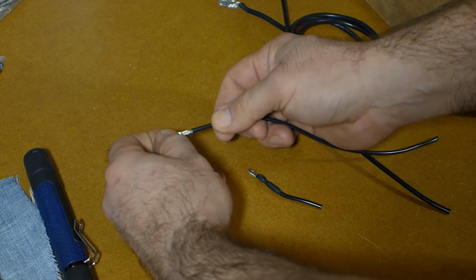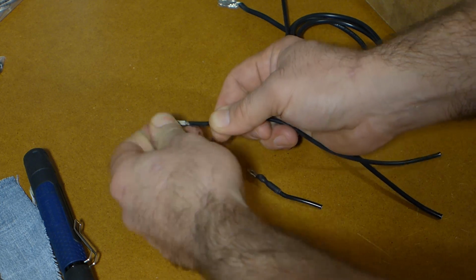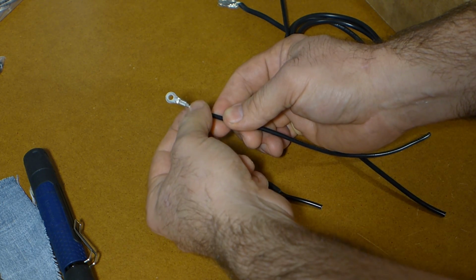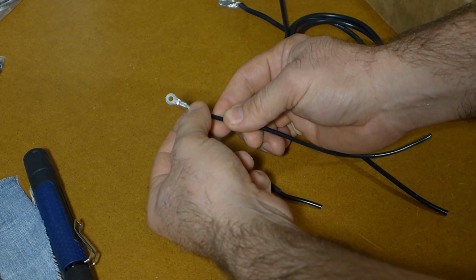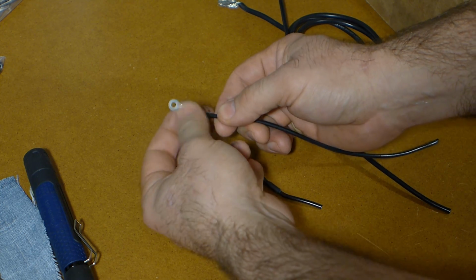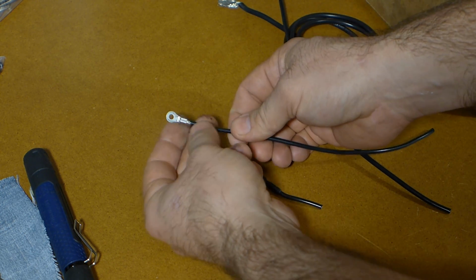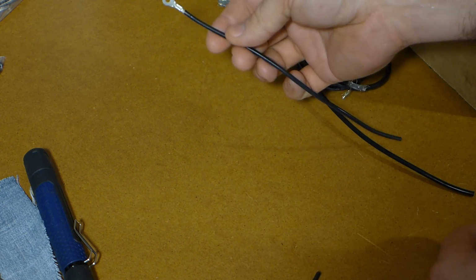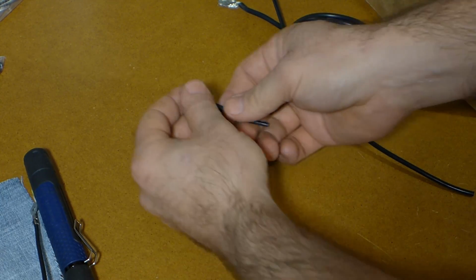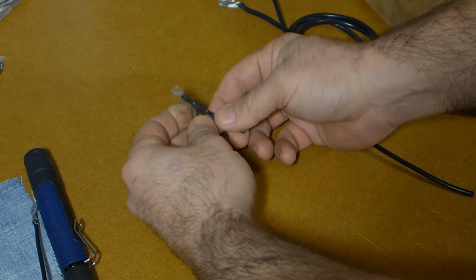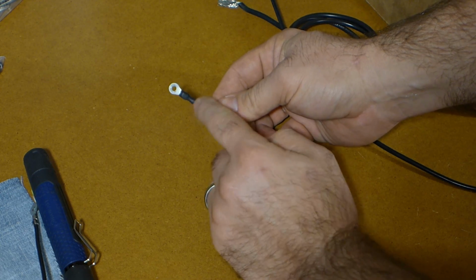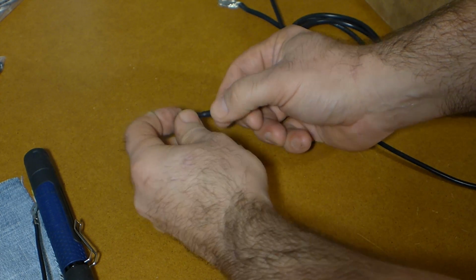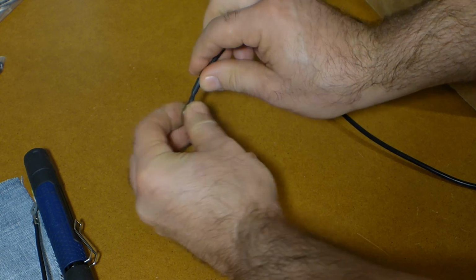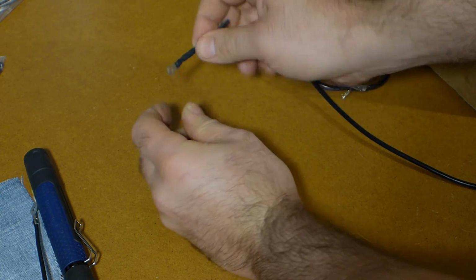And it crimps really well, and that might be a little bit too much space there between the insulation and the start of the terminal. This is just one I pulled out of the junk pile. Once I'm done with that, I'll take a medium wall thickness adhesive lined heat shrink and run that up, and that'll provide the strain relief on the wire. It's actually pretty stiff right there.